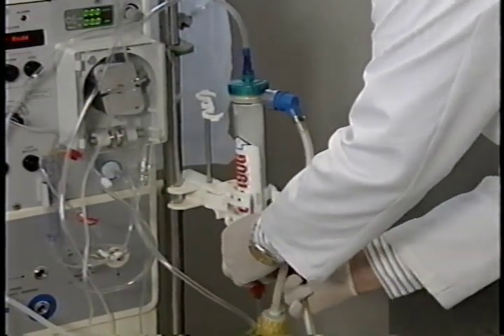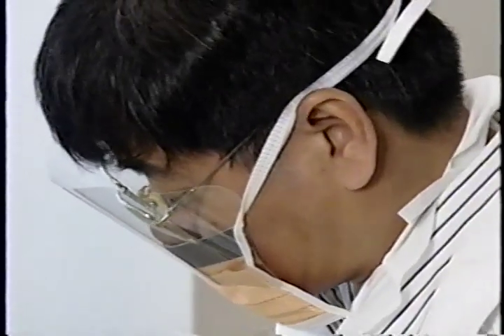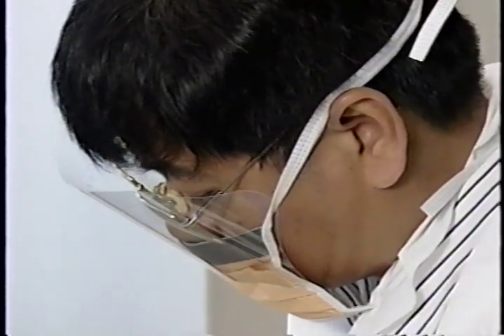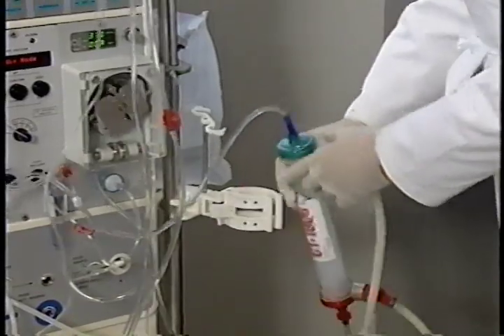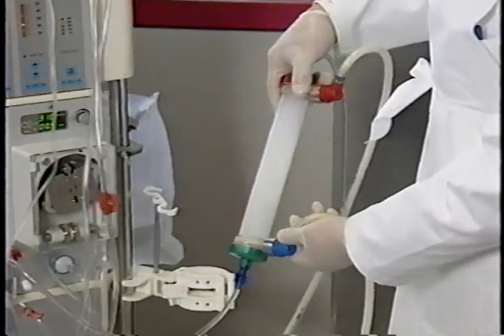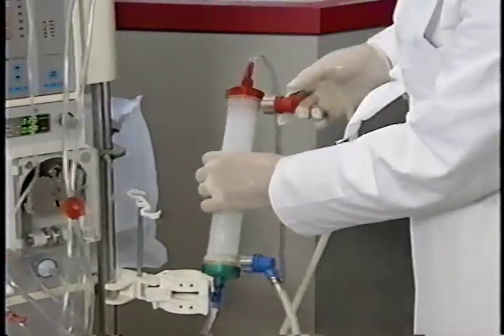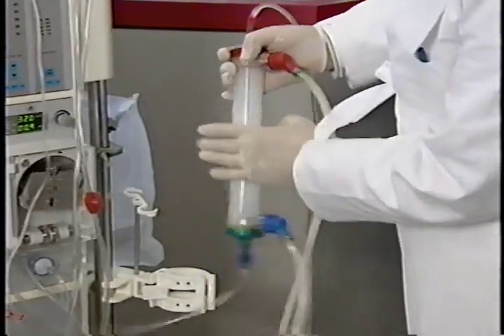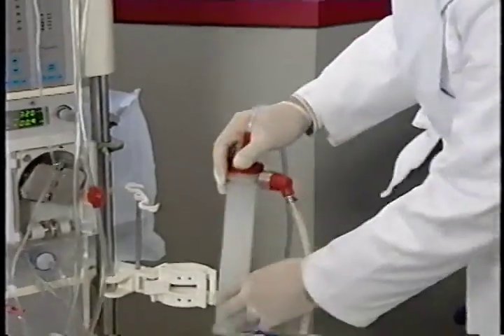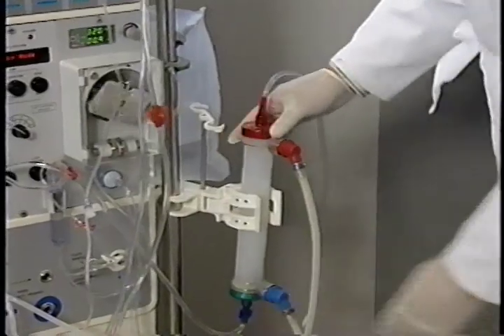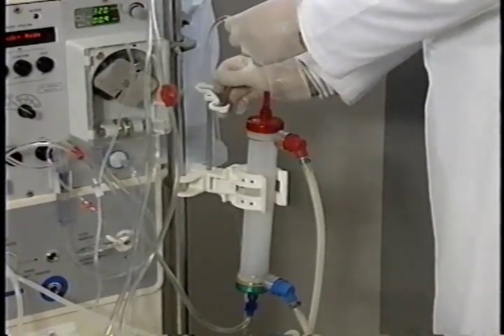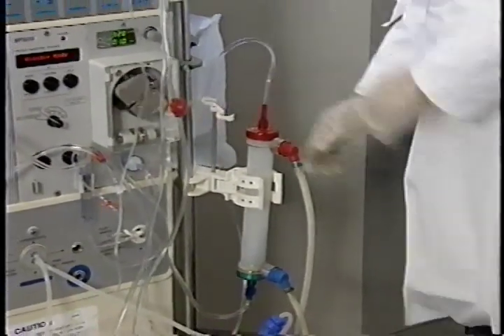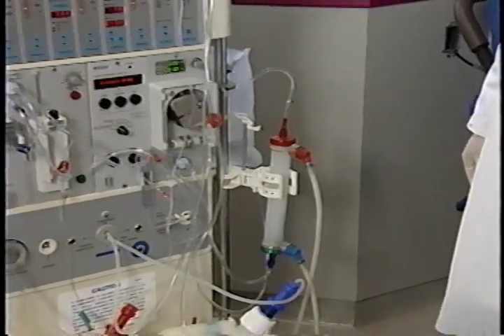To maximize solute clearance, the dialysate flow must be countercurrent to the blood flow. The dialysate flow through the dialyzer is directed upward during dialysis to prevent the accumulation of air bubbles on the dialysate side. When air bubbles are present, the membrane does not come in contact with the dialysate. Diffusion cannot take place, and the efficiency of the treatment is decreased.